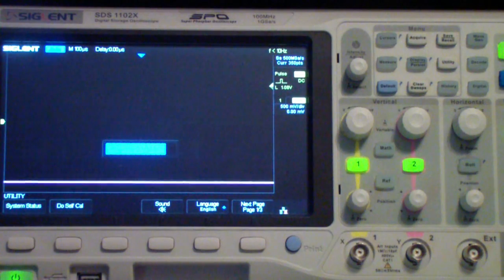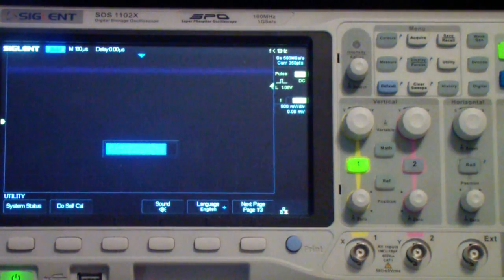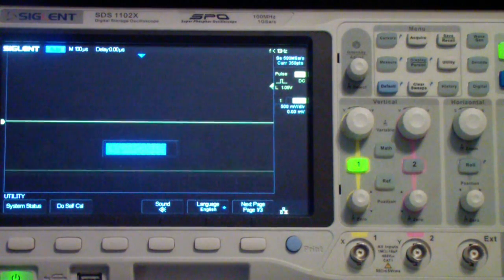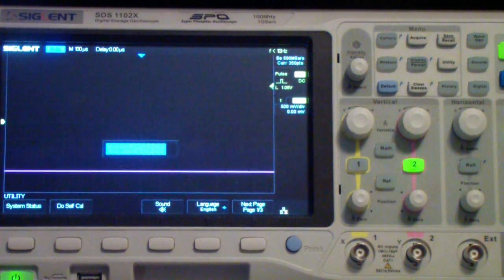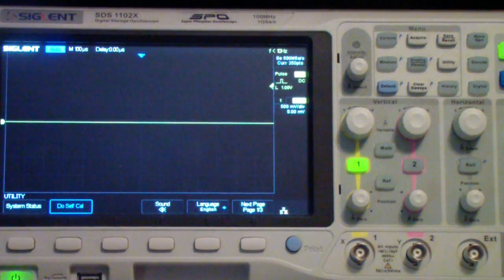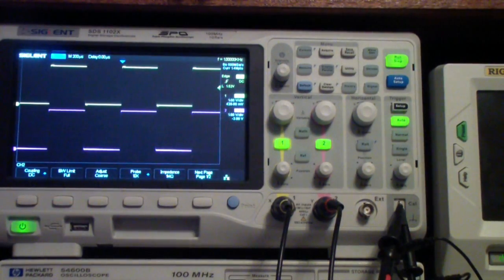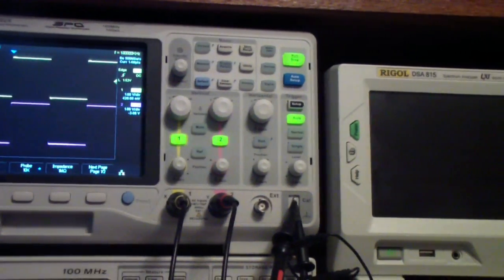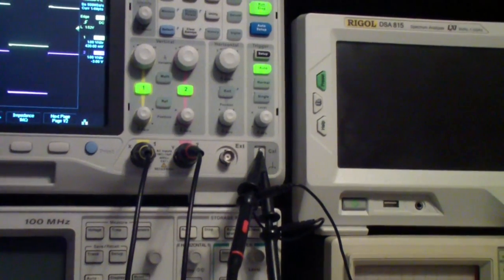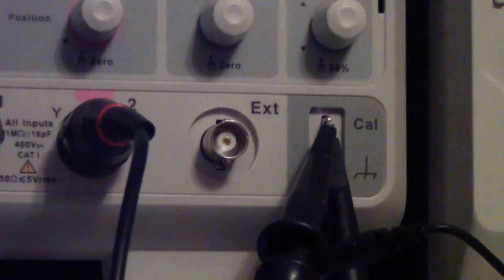Okay, now we're back and it's near the end of its calibration cycle. This has taken about two or two and a half minutes. I haven't actually timed it. And now it has completed and it says press run stop to exit. And so I'll do that up here. And the oscilloscope is now calibrated. Here you see the oscilloscope probes are connected to the compensation signal.